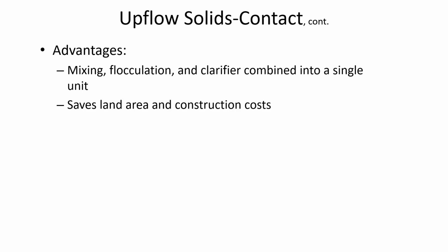In the case of an upflow solids contact chamber, instead of having the water flowing sideways, you have the water flowing up while the particle is settling down. And that has some interesting advantages because as the particle is settling downward, it might encounter other flocs and combine. And it's also a way of saving construction costs by combining a couple of things together at the same time.